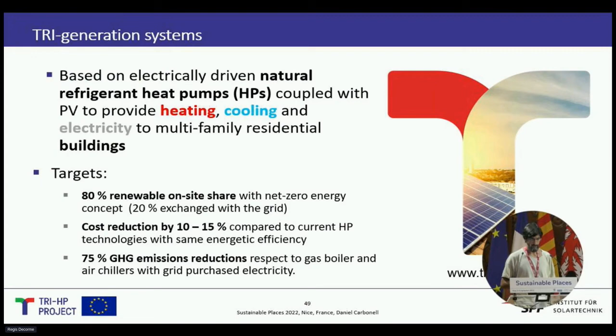So we are aiming at two kinds of systems. One is what we call a dual sourcing system. Here you can see the diagram. Our developments are based on the heat pump and an advanced energy management system. The heat pump is a propane heat pump for which we developed the refrigerant cycle plus heat exchangers. The innovation is that it has an evaporator and condenser, so the heat pump is reversible.